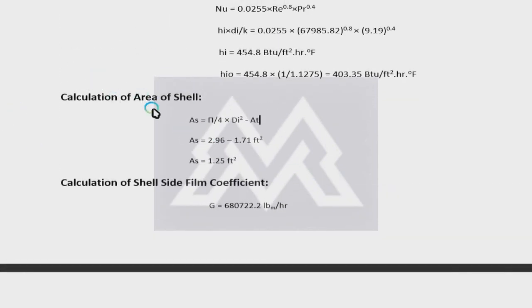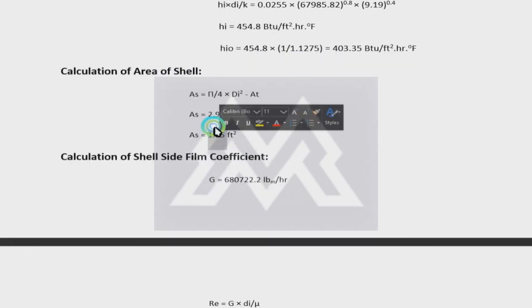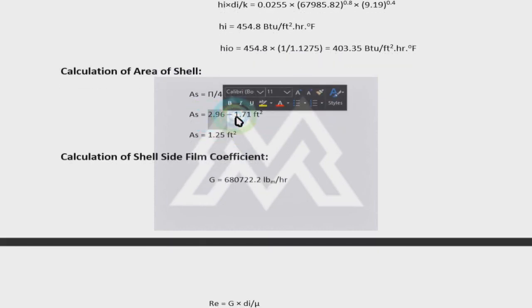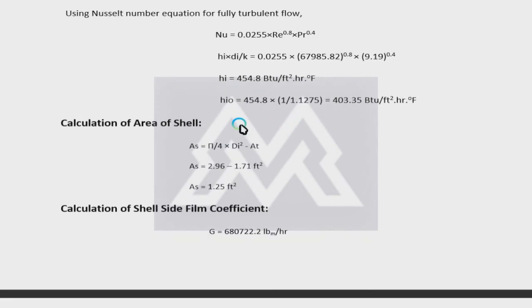The next step is calculating the shell side area. The shell area can be calculated using the effective equivalent diameter of the shell, or by subtracting the total tube area from the total shell cross-sectional area. For example, total shell area was 2.96 ft² and total tube area was 1.71 ft², giving a shell-side flow area of 1.25 ft². The shell-side area can be smaller or larger depending on how many tubes are placed inside the shell.